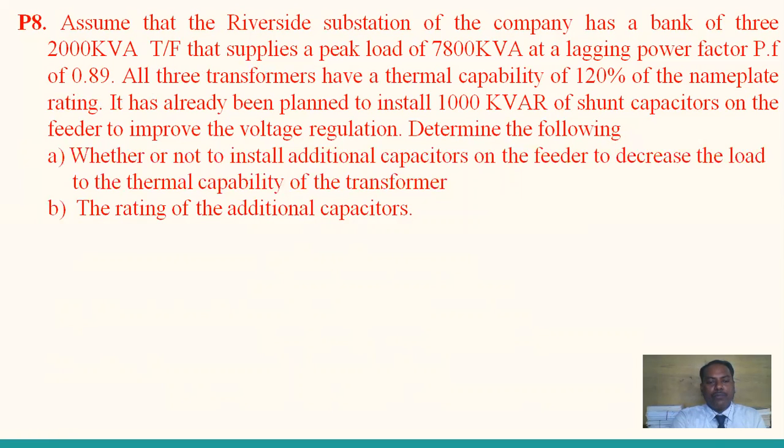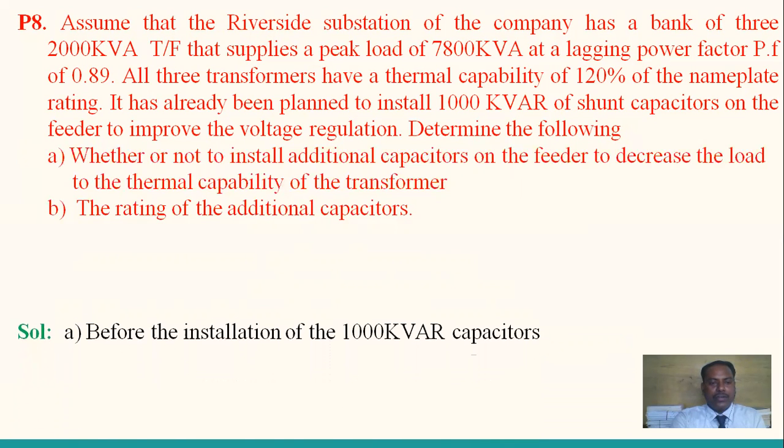Determine the following. Whether or not to install additional capacitors on the feeder to decrease the load to the thermal capability of the transformer. This is the first: capacitors are required or not. And second one, if required, what is the rating of the additional capacitors? So let's go for the solution.